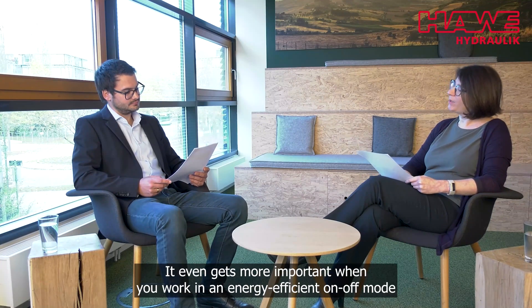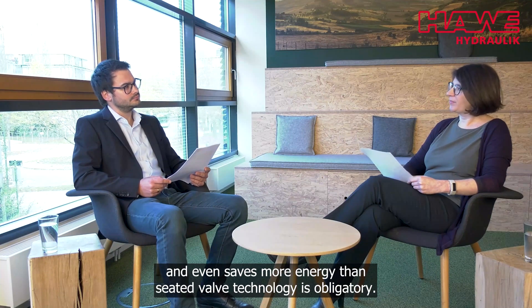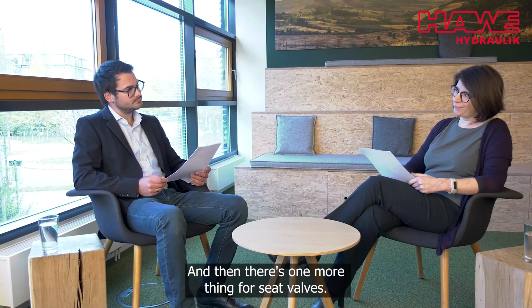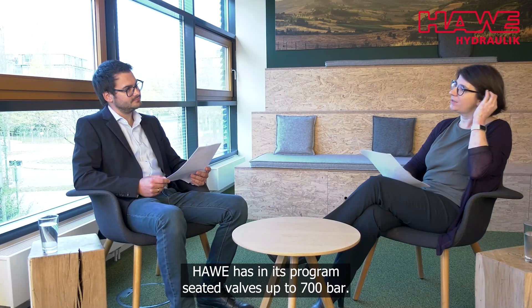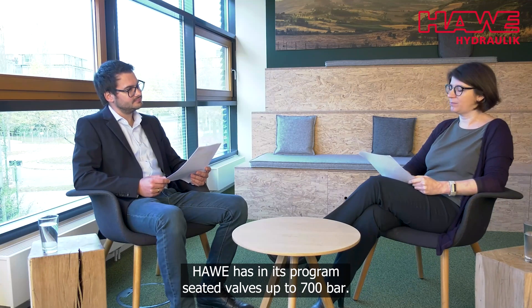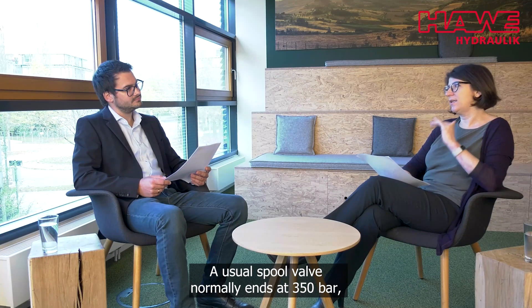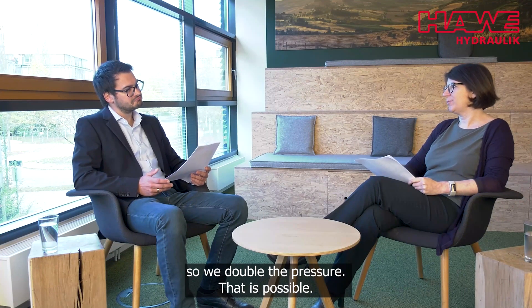It gets even more important when you work in an energy-efficient on-off mode and want to save more energy — seated valve technology is obligatory. And there's one more thing for seated valves: they can withstand a much higher pressure. They go up to 700 bar. HAWE has in its program seated valves up to 700 bar. A usual spool valve normally ends at 350 bar, so we double the pressure that is possible.